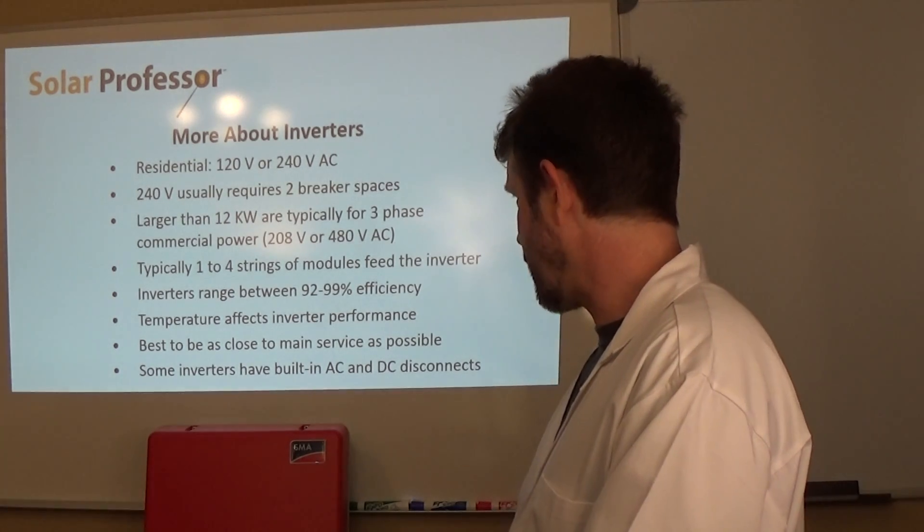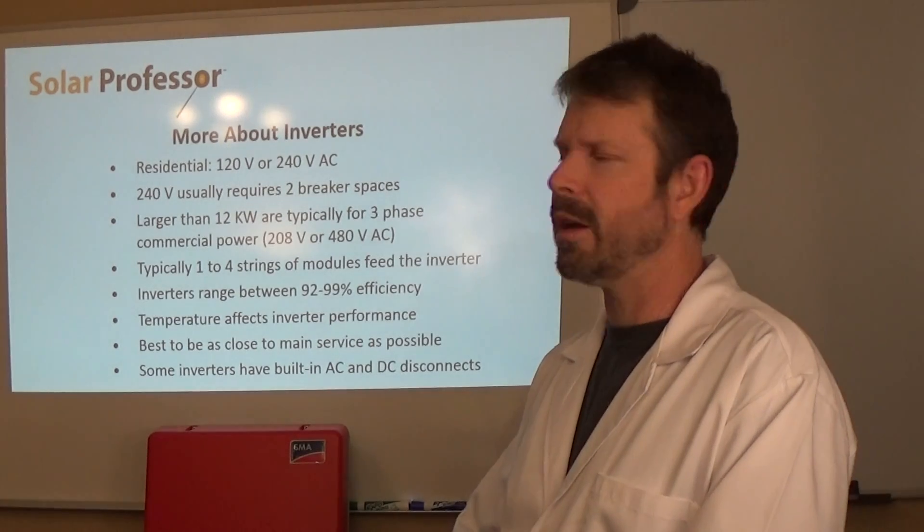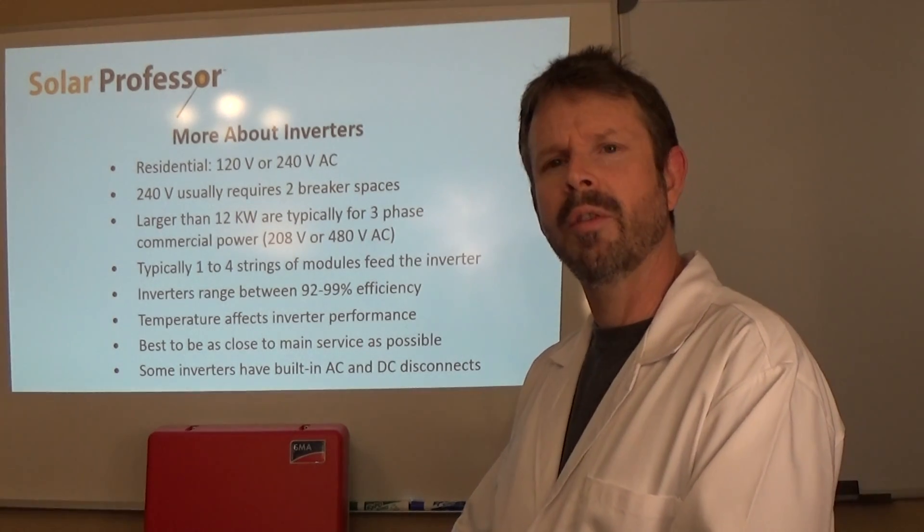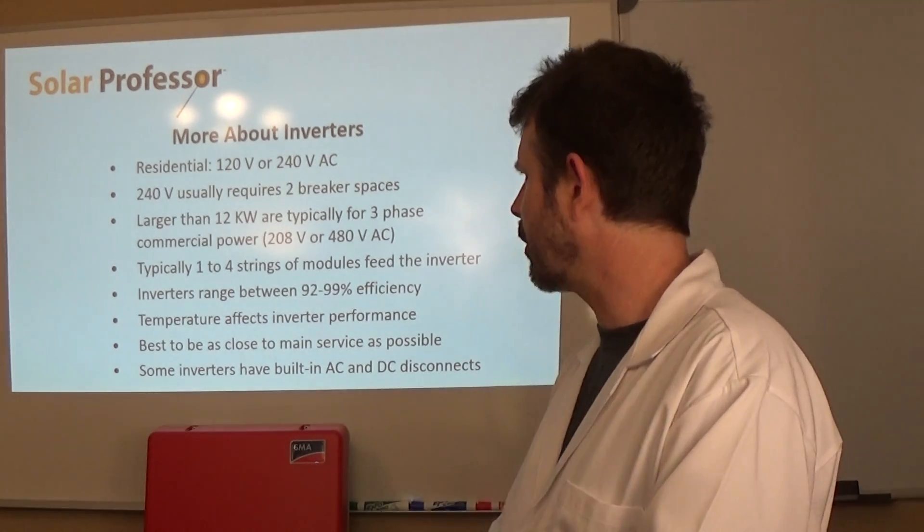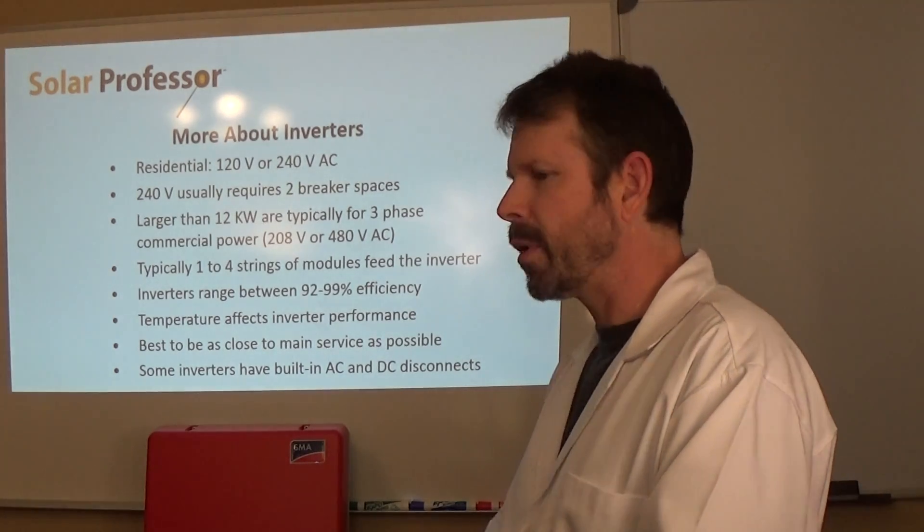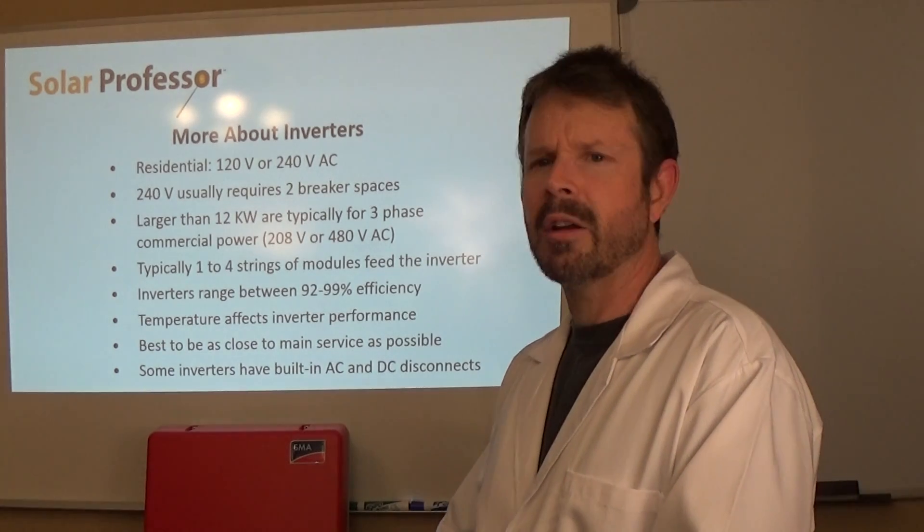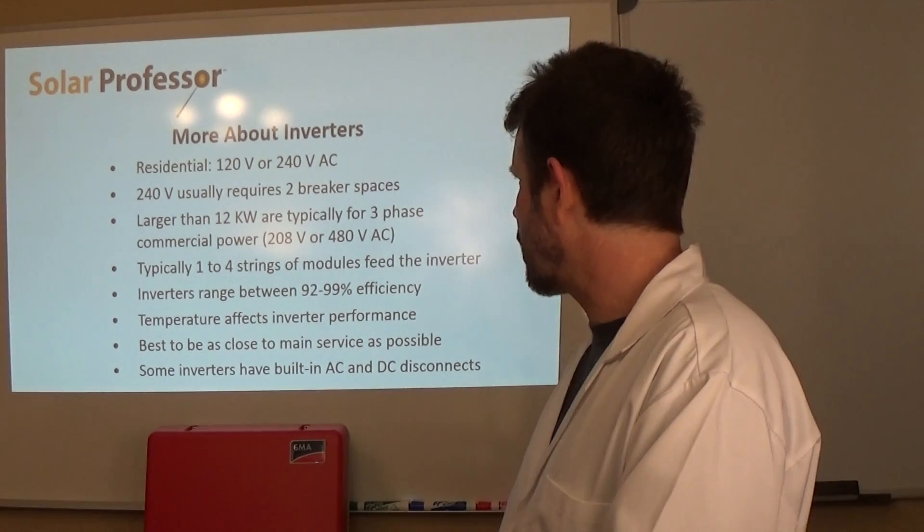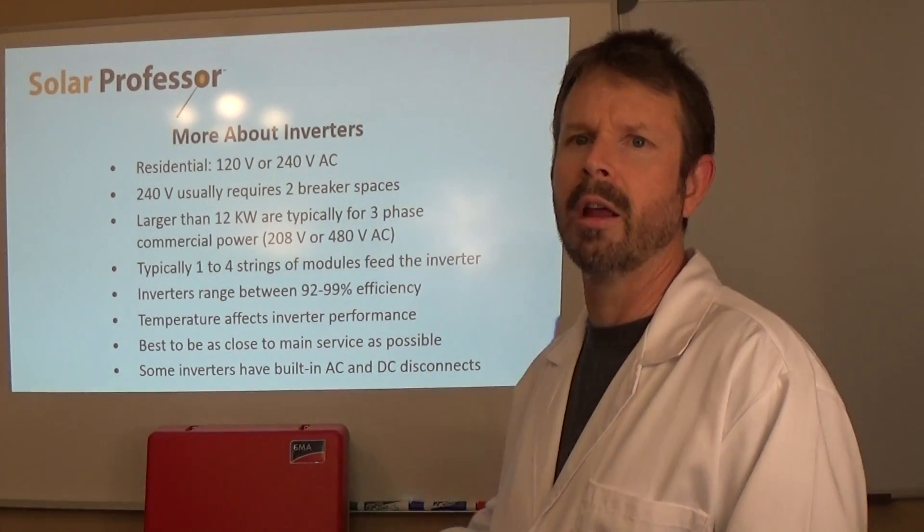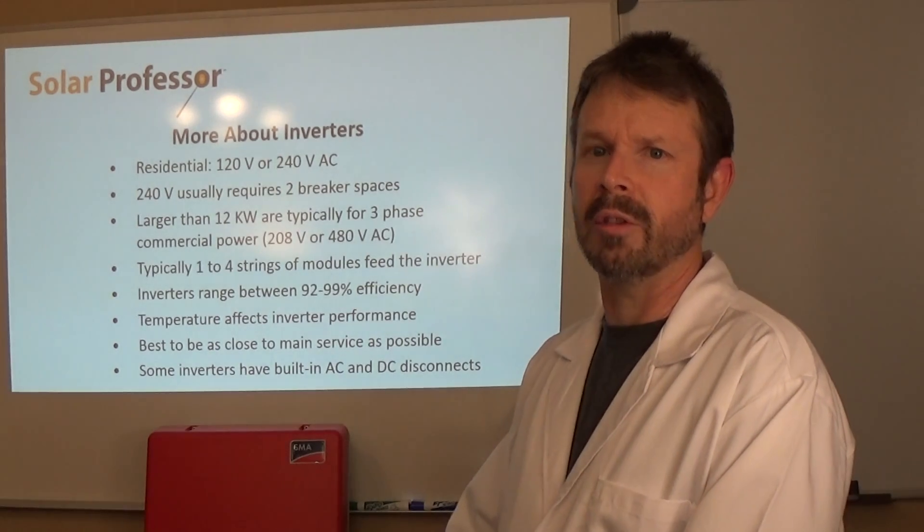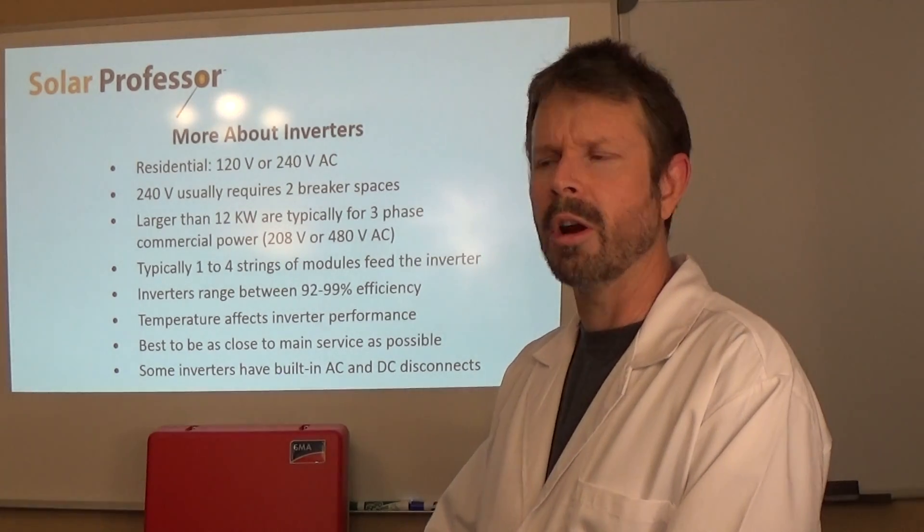Typically one to four strings of modules can feed the inverter and it depends if you choose to do a combiner box or not. Inverters range between 92 and 99% efficiency, some of the older off-grid inverters were 85% efficient. Inverter technology has come quite a long way in the past 10 years and we're getting inverters that are almost 99% efficient. That means its ability to convert from direct current to alternating current, 99% efficiency is pretty darn good.